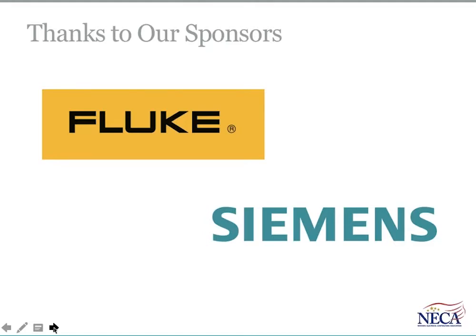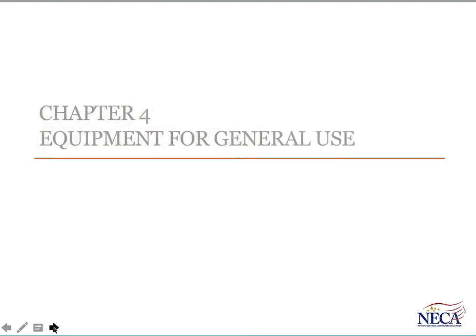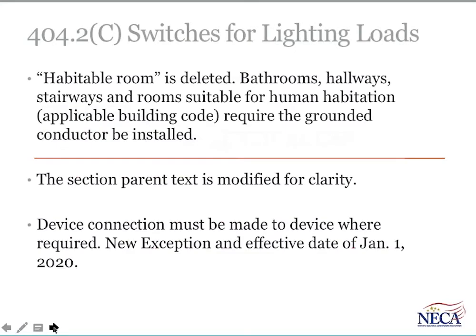So with that, I'm going to get right into it and start on some changes in Chapter 4. Chapter 4 of the NEC is titled Equipment for General Use. The first article where we saw significant change is Article 404. Article 404 covers switches, all sorts of rules for switches, but the change in 404.2(C) deals with switches for lighting loads, and it deals with that recent set of changes requiring the neutral or grounded conductor be brought to each switch location for a lighting load.